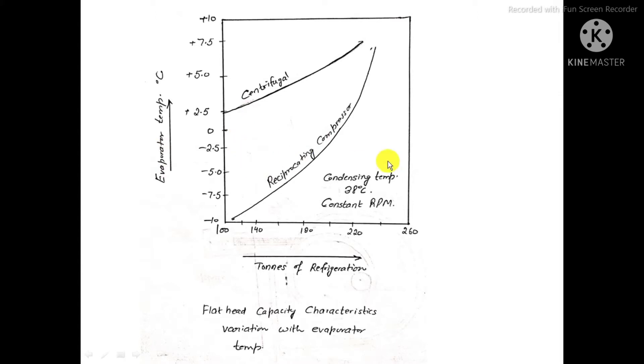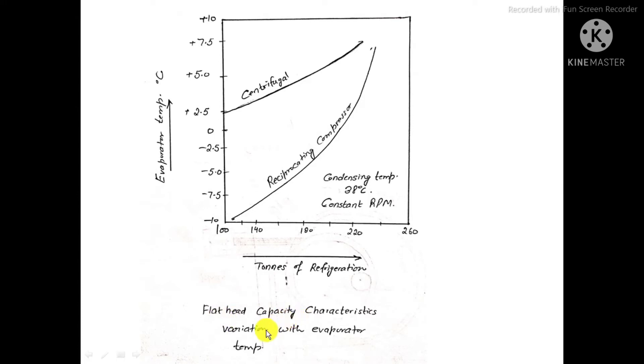This graph illustrates a great deal about reciprocating and centrifugal compressors. On the y-axis we have evaporator temperature in degrees Celsius, and on the x-axis we have tons of refrigeration — 100 tons, 140 tons, 180 tons — representing capacity. This graph shows flat head capacity characteristic variation with evaporator temperature. The centrifugal compressor curve is much flatter as compared to the reciprocating compressor curve.